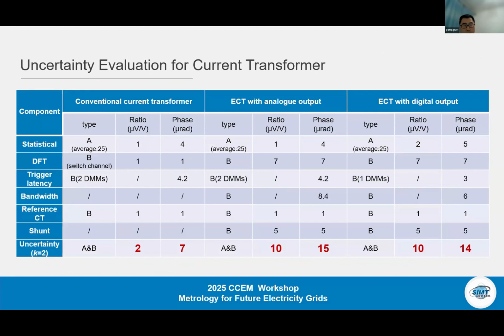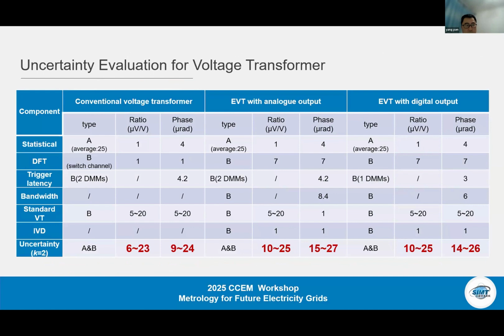So this is the final uncertainty evaluation for the current transformer. The calibration platform applies to conventional current transformers and also ECT with analog output and also with digital output. So this is for the voltage transformer, both for conventional voltage transformers and also non-conventional voltage transformers and also with digital output.